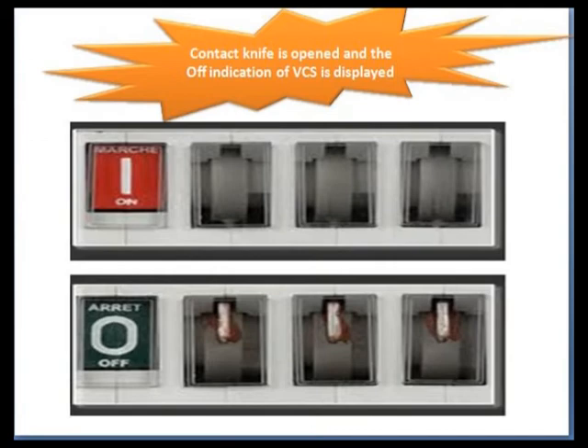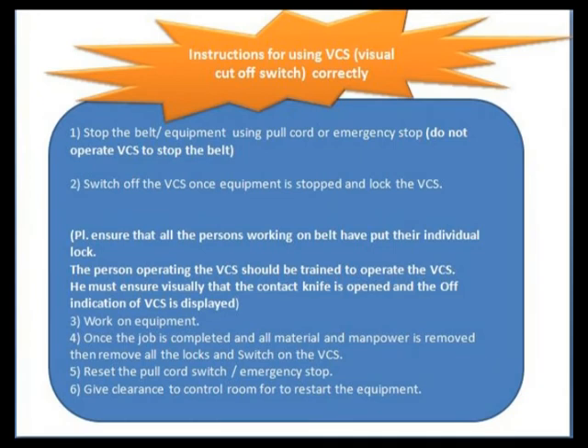Here are the operating instructions for VCS. Always first stop the equipment using an emergency button or pull cord — never operate VCS directly without stopping the equipment first. Apply the emergency stop, then switch off the VCS. Once the equipment is in a stopped condition, ensure that all persons working on the belt have applied their individual locks. The person operating the VCS must be trained to do so.